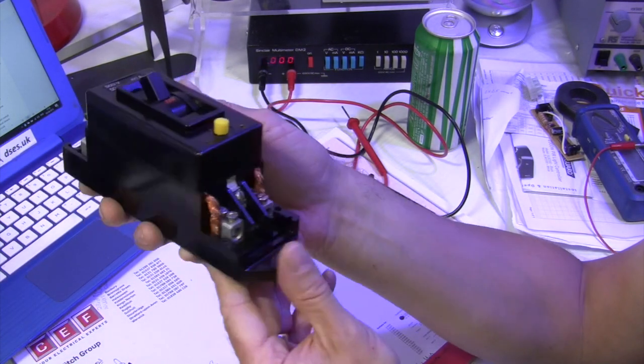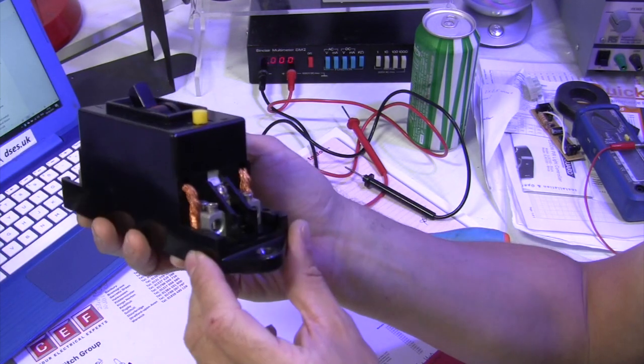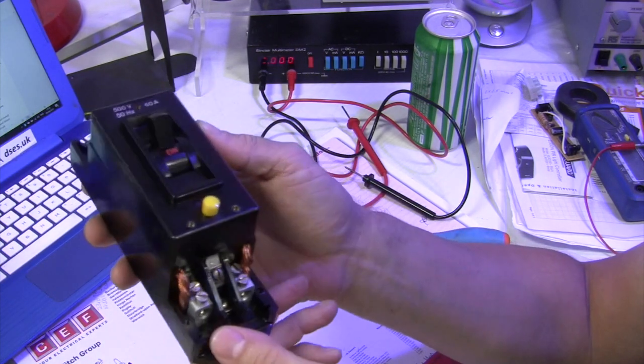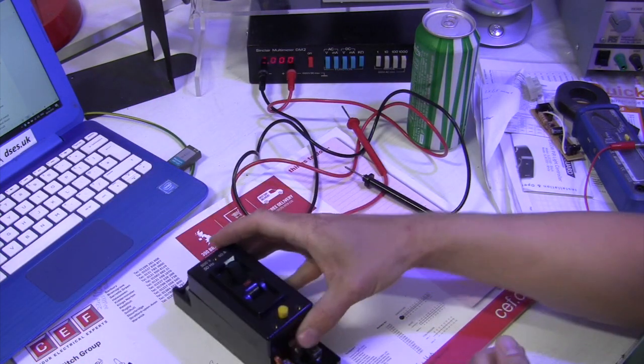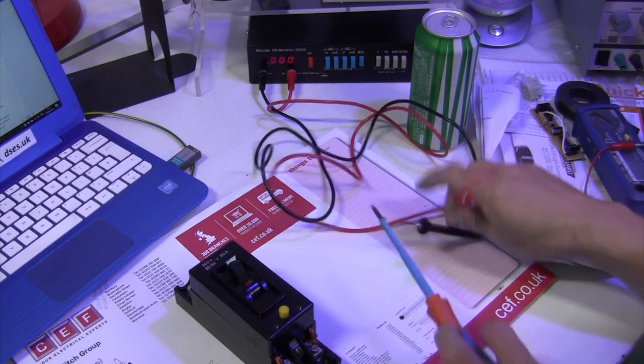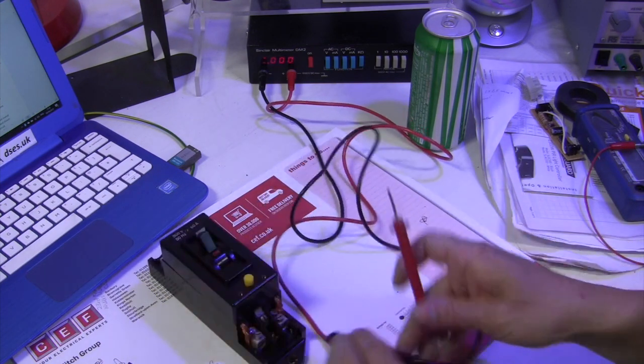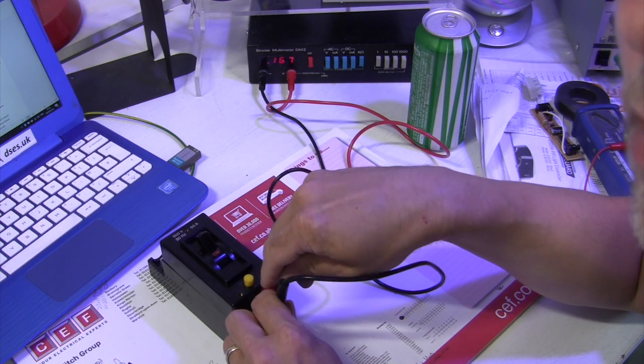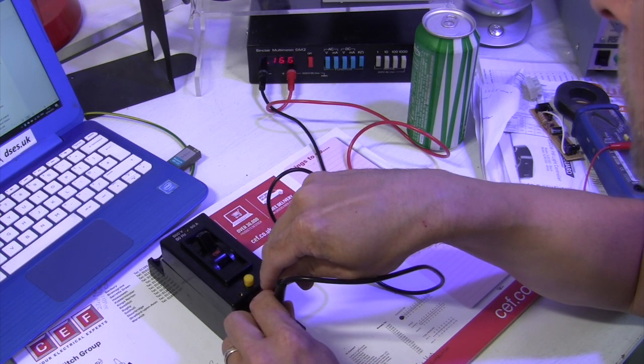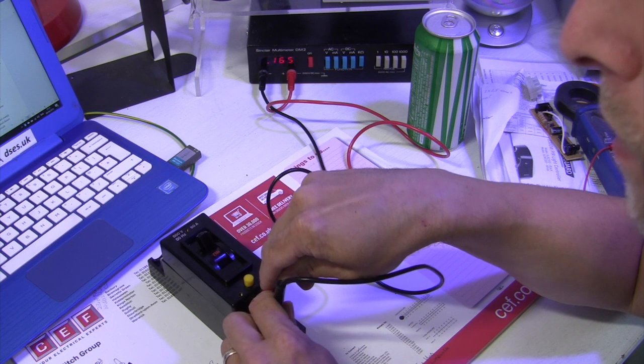And I notice there are two other terminals under this bottom cover. These are labelled E and F. Now there's a coil across these terminals and if we stick an ohmmeter, my trusty old Sinclair here, across those two terminal positions, we can hopefully see on the camera a reading of around 166 ohms across that coil.